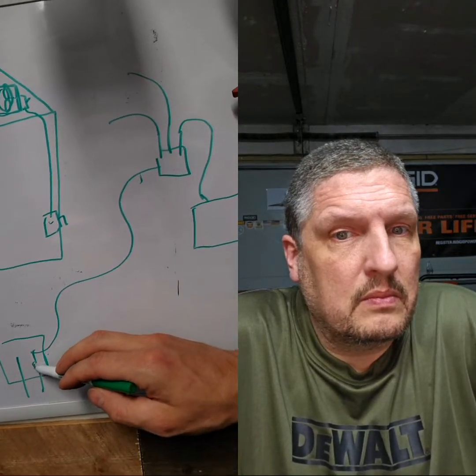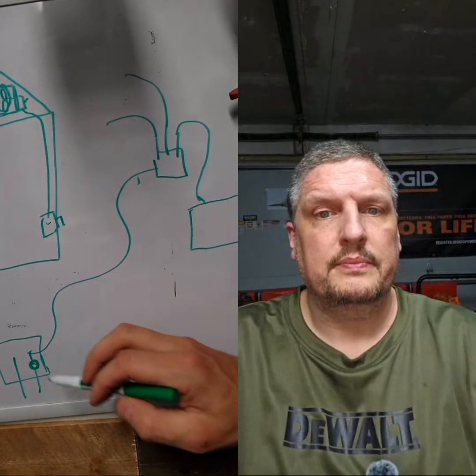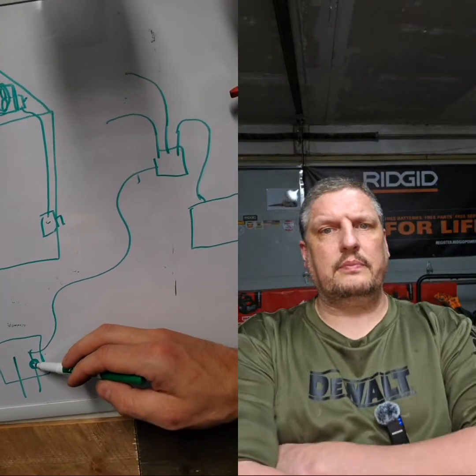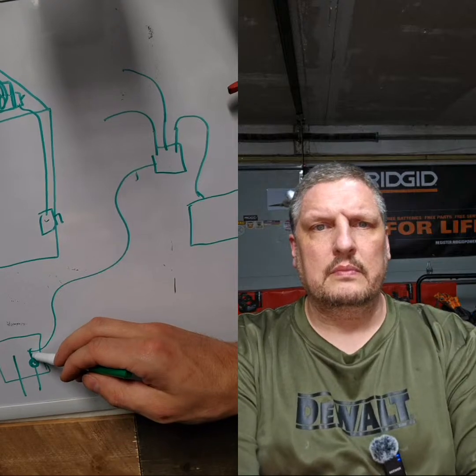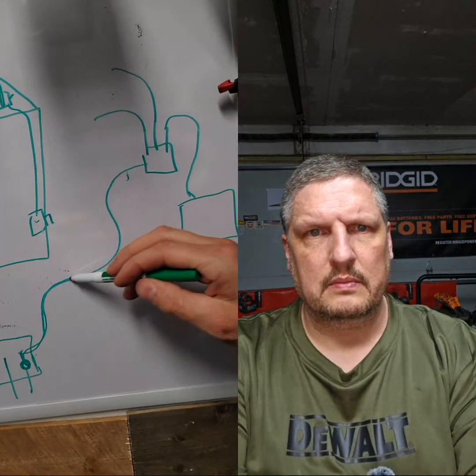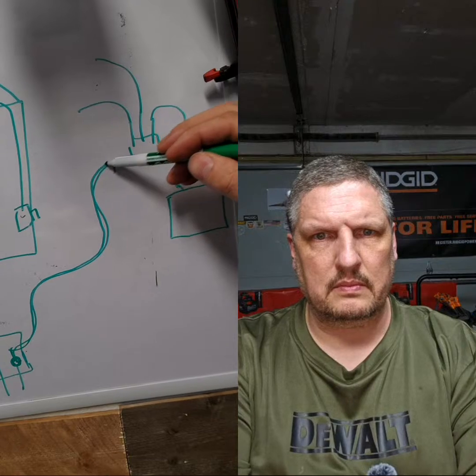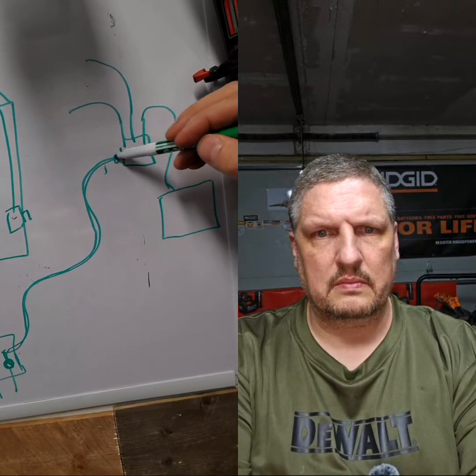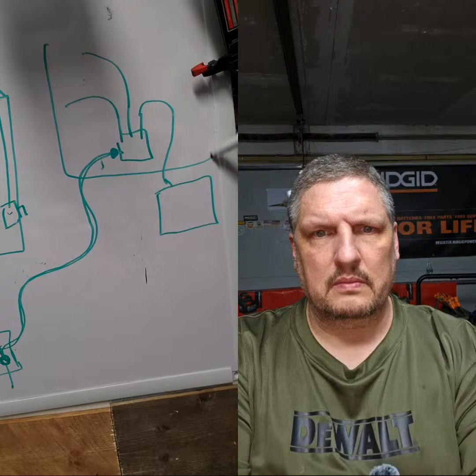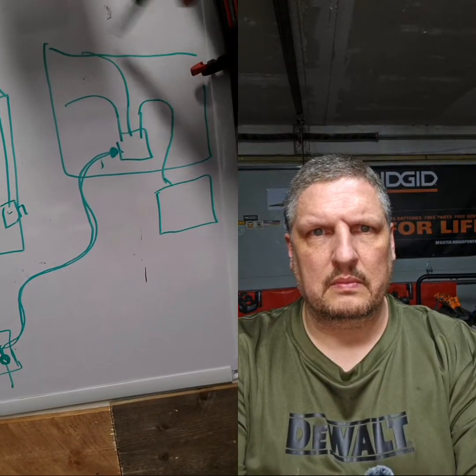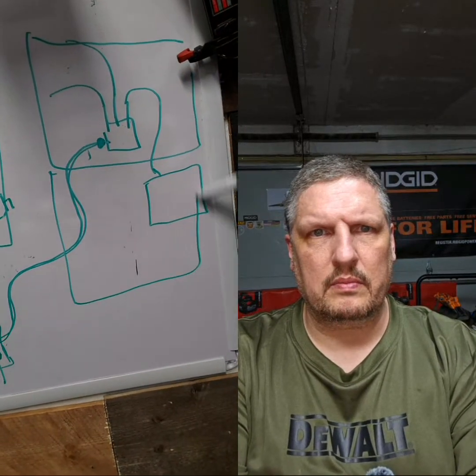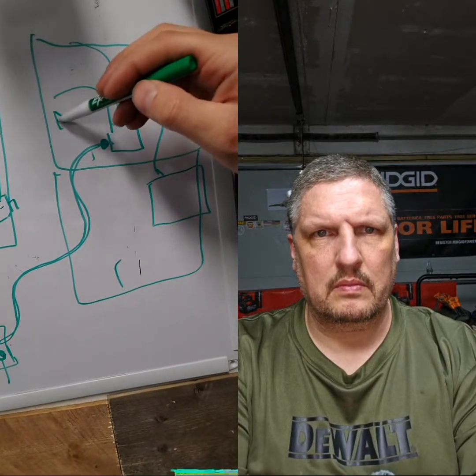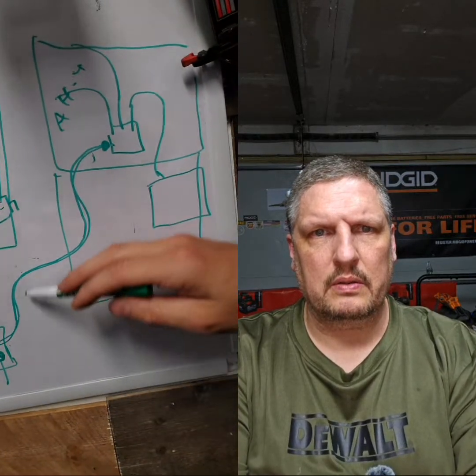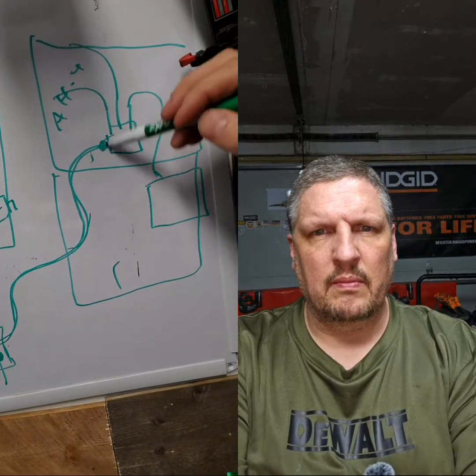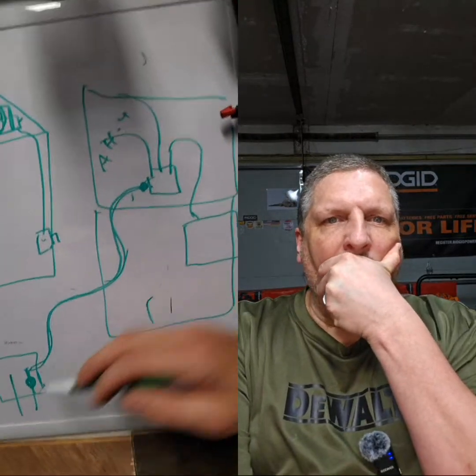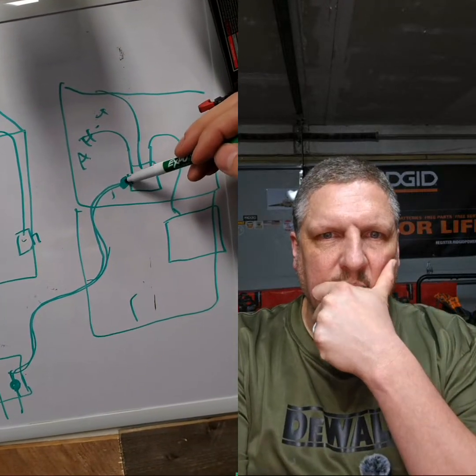What you should do is take a clamp to the outside and run that continuously with number 6 all the way back up to this manifold in the attic. So this is a different area - this is the attic of the house, right? Yeah, and then this is level 1, this is the attic, whatever. You're gonna run that number 6 with that gas line all the way up here. That way, this here is the same potential as your manifold.